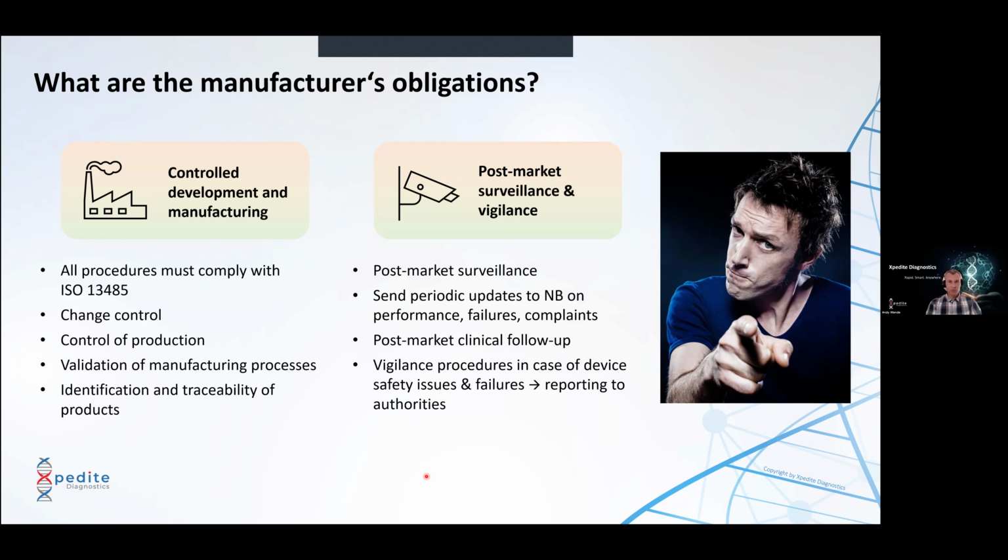Then there are things like this post-market clinical follow-up, where in certain cases the manufacturer has to make some effort to find out if there are changes to the clinical performance of the device. And maybe some new background information because other, let's say, mutations are becoming known. So you might have to adjust your assay to these new mutations. And then last but not least, the vigilance procedure is also very important, especially if you really face some safety issues with your instruments or devices in the market. So that's a lot of things.